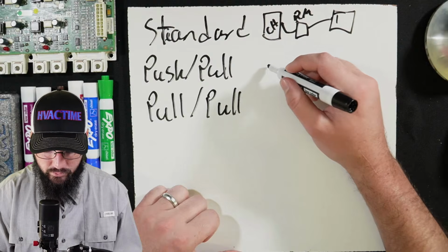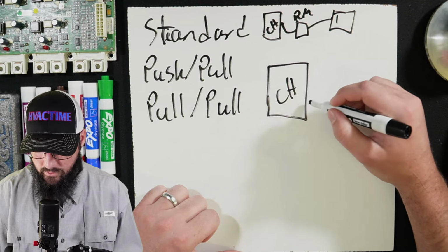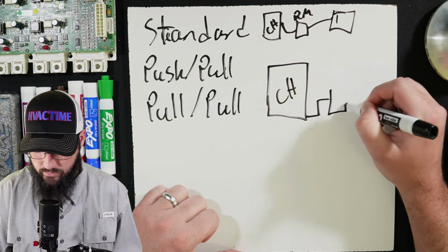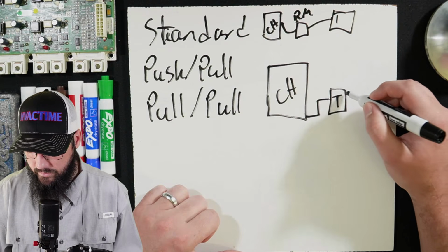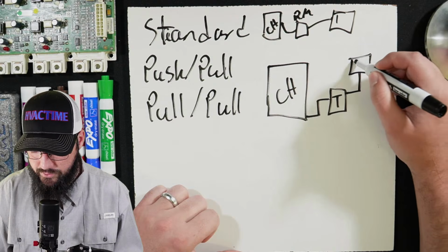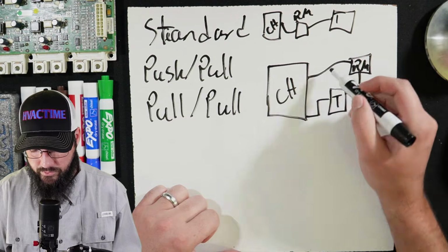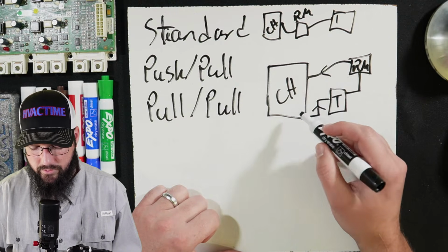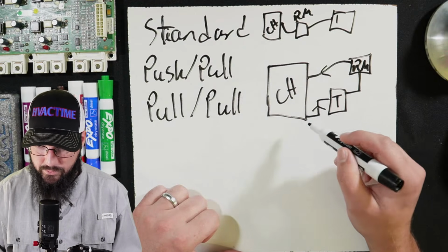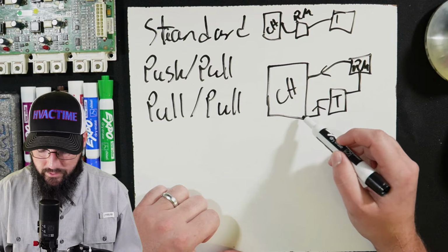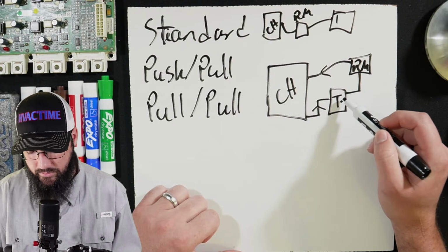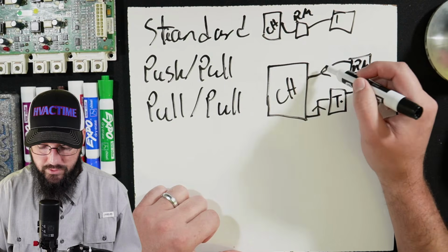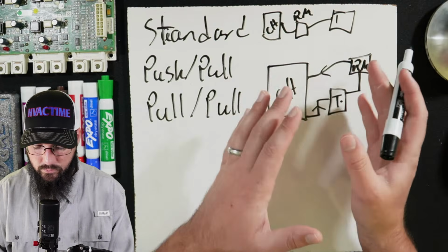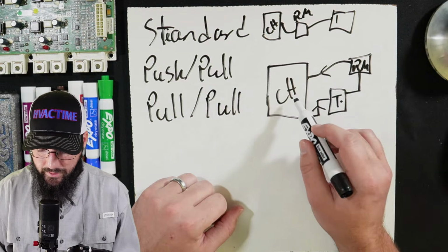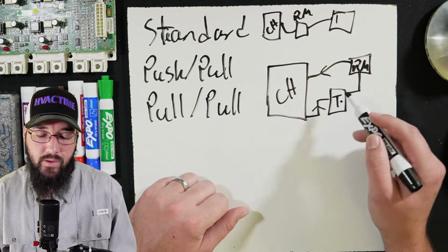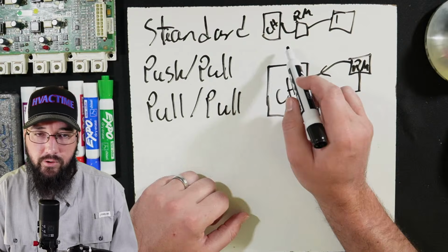Covering push-pull first, we have our chiller. We come out of the chiller into our tank, out of that into our recovery machine, and then back into the chiller. So we're flowing this way. This is the first stage of the process. Both of these are a two-stage process. We're pulling the liquid out of the bottom of the chiller into a tank that is catching that liquid, and we're pulling vapor off of the recovery cylinder and pushing that vapor back into the chiller. It creates a push-pull cycle. We're pushing and pulling at the same time. That's the general theory, and we're collecting the liquid refrigerant here. Eventually, once all the liquid is out, we switch back over to a standard recovery and pull all the vapor.